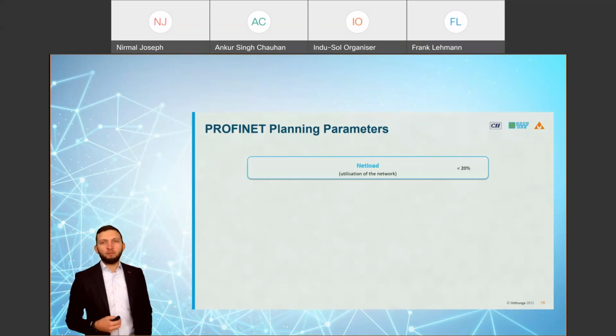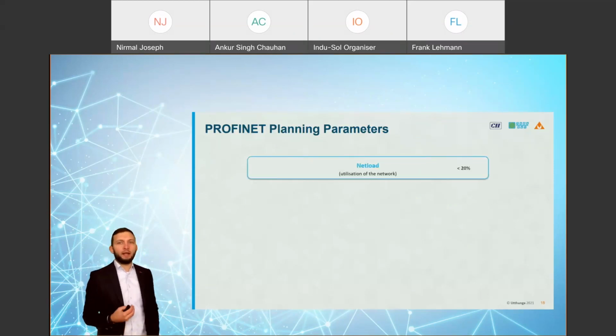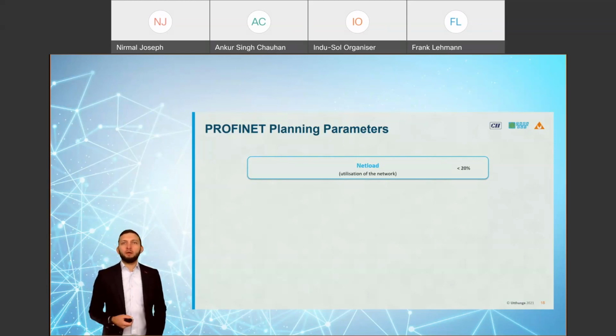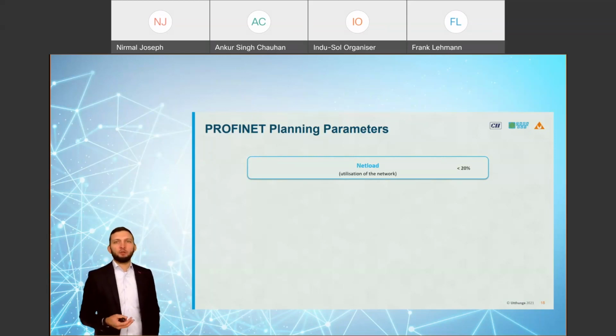Let's start with net load. The net load is the utilization of my network, or the used bandwidth from my application on the network. For example, my PROFINET network can support a transmission speed of 100 Mbits per second, and from this 100 Mbits, I should use up to 20%, or up to 20 Mbits per second, of this provided bandwidth.